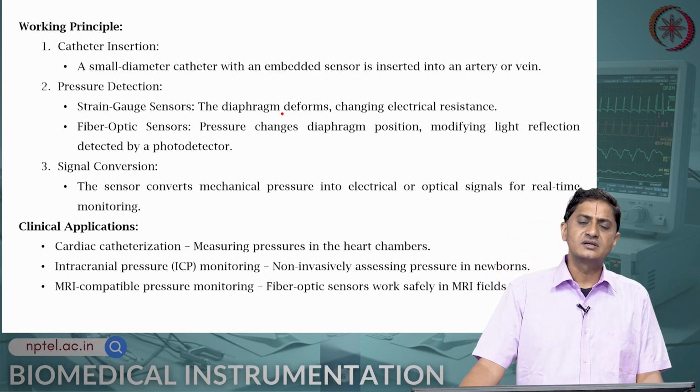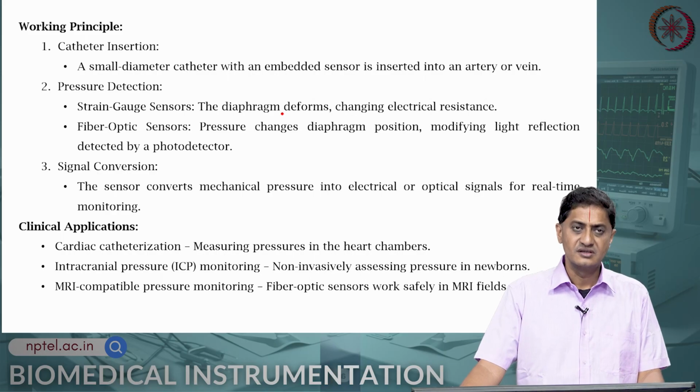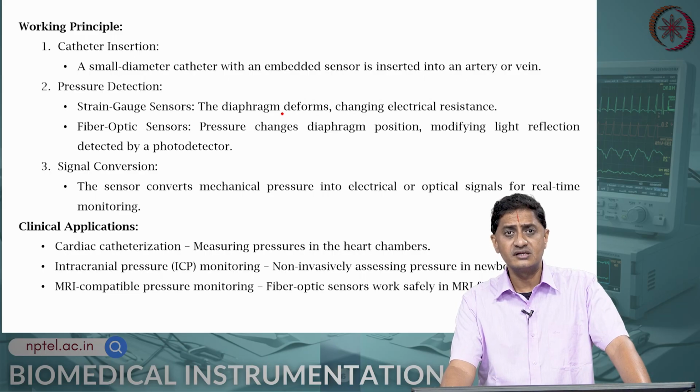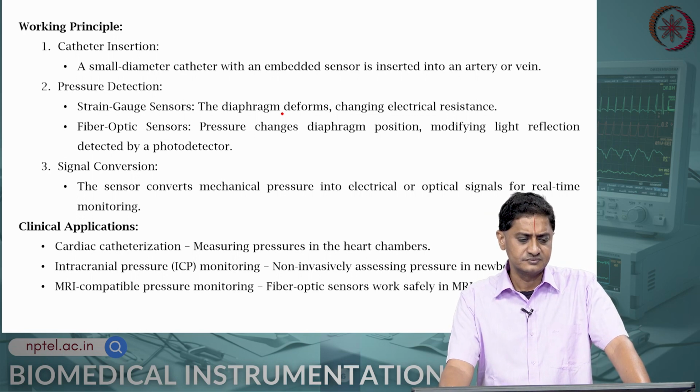Now, let us look at the working principle of the catheter tip sensors. The first step is to insert a small diameter catheter that has an embedded sensor into the artery or vein of interest. First of all, this is a clinically sensitive procedure that only qualified medical professionals can do.